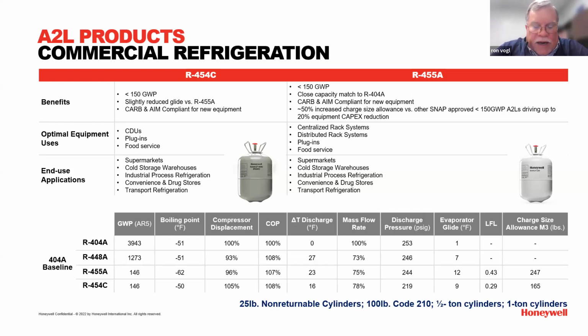Now if the requirement's in a warehouse, that's pretty easy, right? Let's say an A1 leaks and it picks it up, you turn the fans on, it's not the end of the world. If it's an A2L, and we're talking now where you've got working equipment like an equipment room, the requirement could be that you need to shut down equipment, close solenoid valves, that sort of thing. So again, like Eric said, a lot of stuff is in transition.